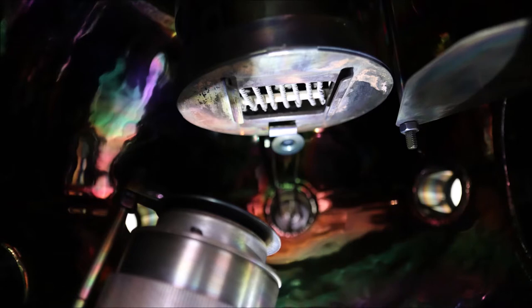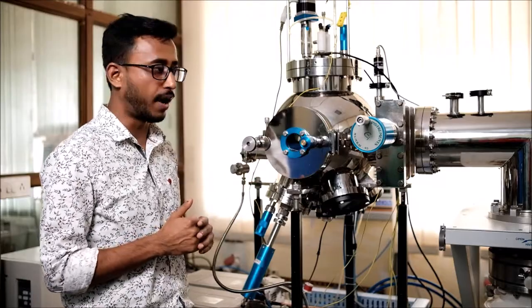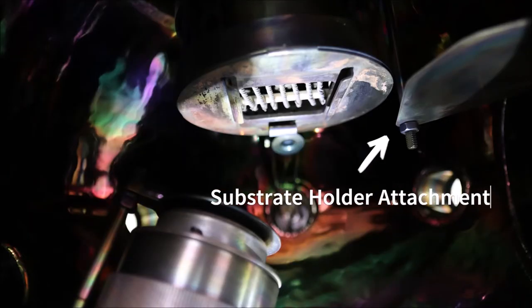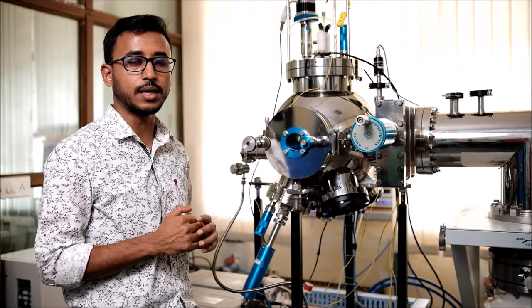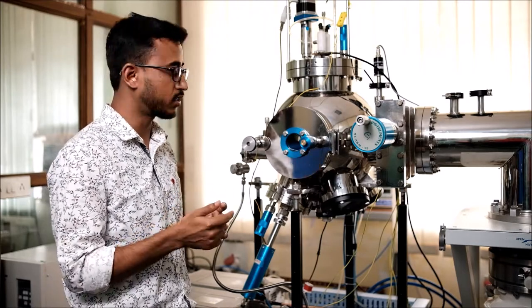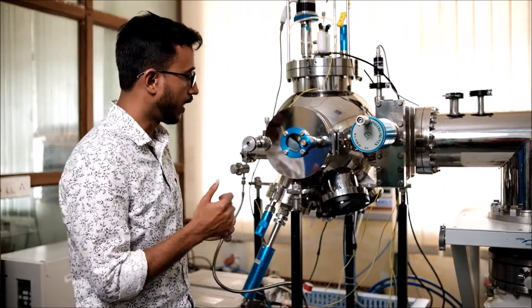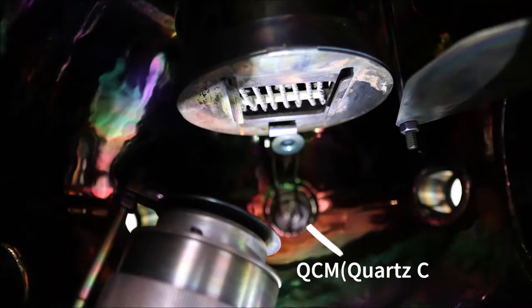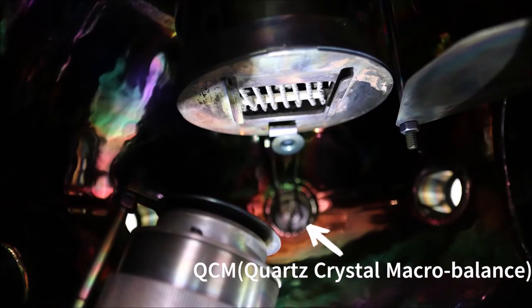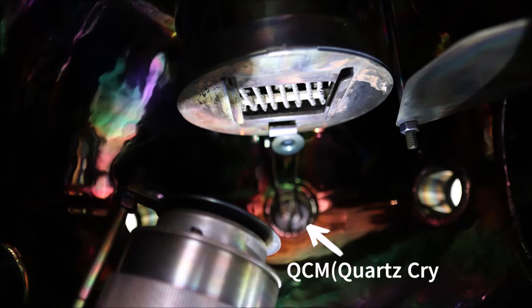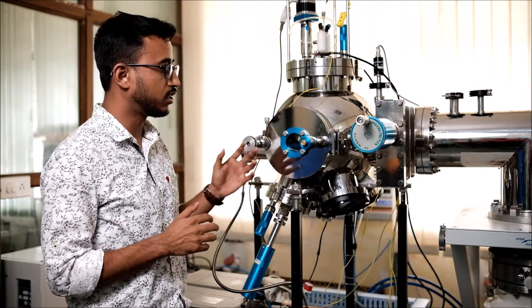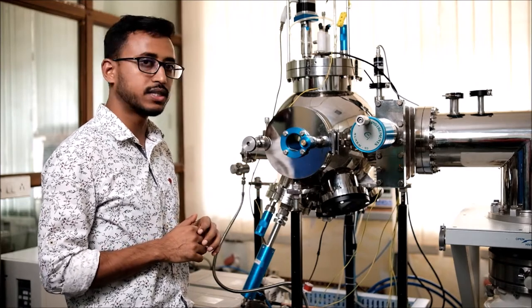At the inside of the chamber, the spring-like structure is the heating coil, which is responsible for heating the part. And then at the bottom of it, the groove you see, there we hold the substrate holder. This also rotates with a controller. And at the back of the substrate rotation holder, we see a disc-like structure. This is the quartz crystal microbalance system. This is used to monitor our film's thickness.